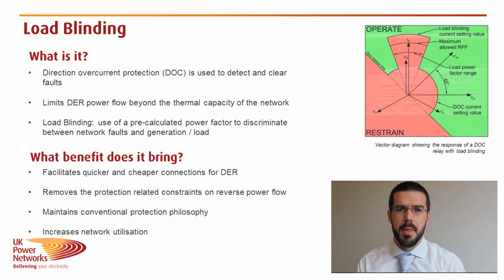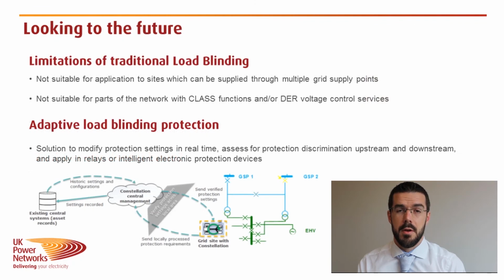As said before, load blinding relies on load or generation power factor being clearly distinct from that of a fault. And this isn't always the case, especially if the distributed generation is providing reactive power services or other services such as those being trialled within our Power Potential project.